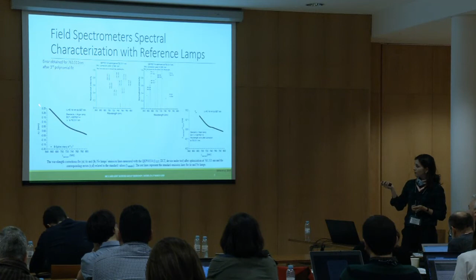And a solution here, for example, would be to combine 2 lamps, because these are the most often used, neon and argon, and to couple them. In this way you can do the correction specifically for the wavelength that is closer to oxygen A, and use the other lamp to do the correction for the other line. This can be an option. But still you are not correcting perfectly for that specific wavelength corresponding exactly to the oxygen bands. And here you have the different errors that you can obtain for different spectrometers. This one is the case of a high resolution spectrometer, and this is for 2 reflectance spectrometers. And you can see that the errors are between 0.1, let's say, up to, depending on the configuration, 0.5, let's say.